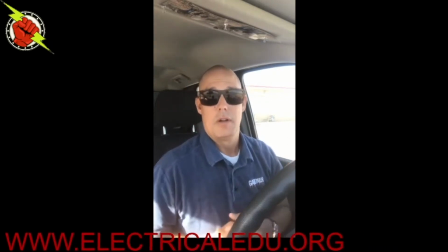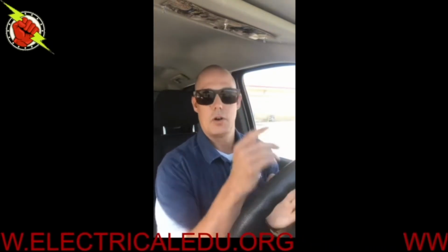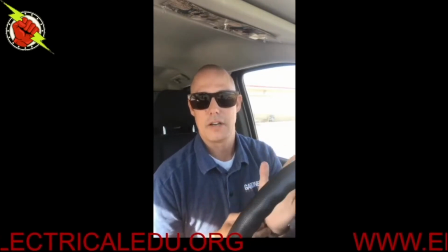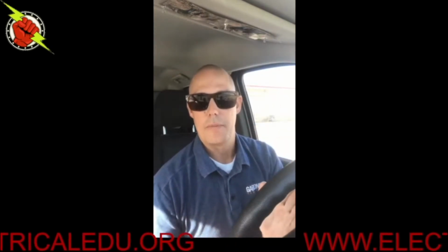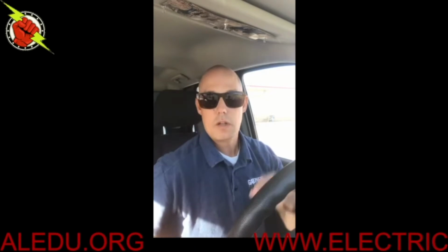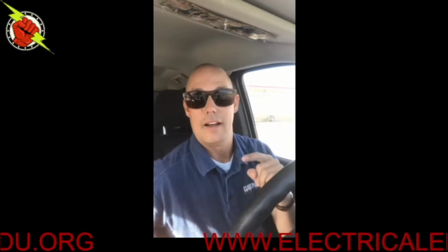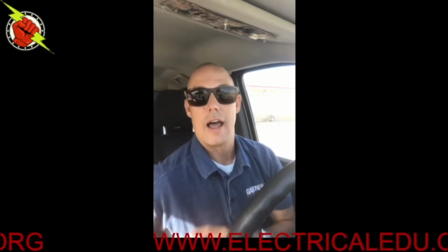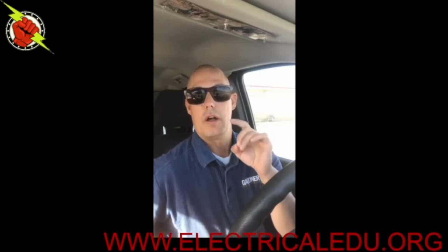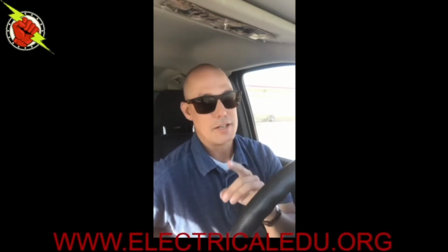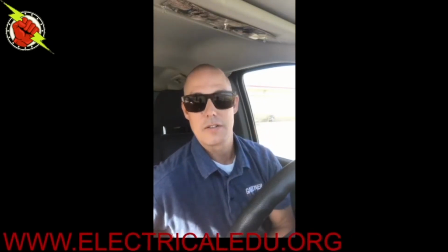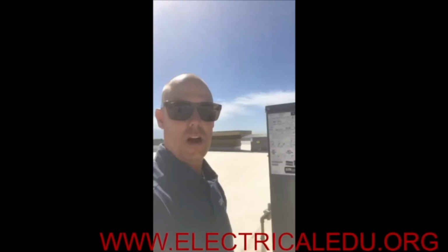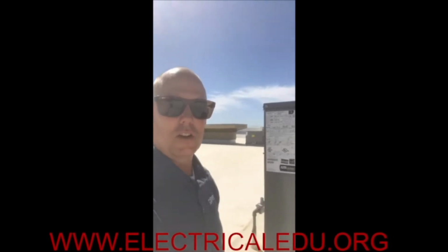It's not uncommon. Sizing wire, you don't just have to go to table 310.15, find the 75-degree column, and go off your ampacity on every load. So stay tuned, and I'm going to teach you today how to size for an air conditioner. It's different than the way you size for anything else, and I'll give you the codes and how to do that.